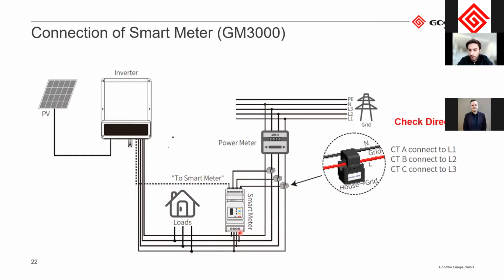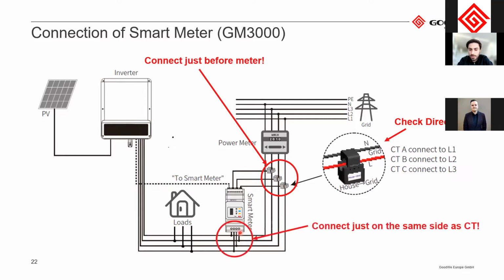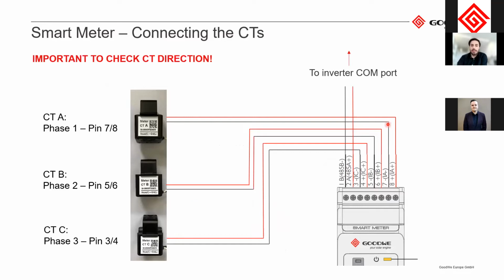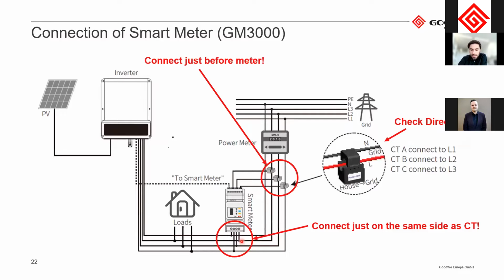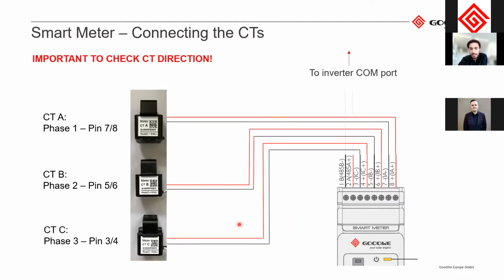I will also show that, yeah, exactly, connect just before the meter and check the direction, and also connect on the same side as the CT so that you make sure that loads are located there. One thing that could be a bit tricky, I can show that again here, is that each CT should be connected to a specific line, and the corresponding line should also have the voltage sense here, and the direction on how you connect the CTs here on the upper part is different from how you connect the voltage sense. So pay attention to this here.